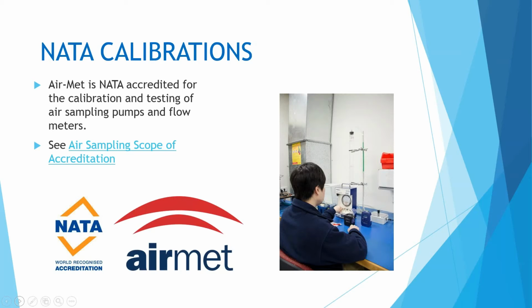As part of this accreditation, we can also test air sampling pumps in accordance with the requirements of NATA's application document Annex B, so asbestos fibre counting. So under the workplace pump calibration section, for this service we generally do back pressure tests up to 7 different flow rates depending on your request. And for those of you who are doing asbestos monitoring, you might be interested that the testing we have done on the new SKC AirCheck Touch pump that Debbie just showed shows it has no problems meeting the NATA back pressure requirements of 4 litres a minute.